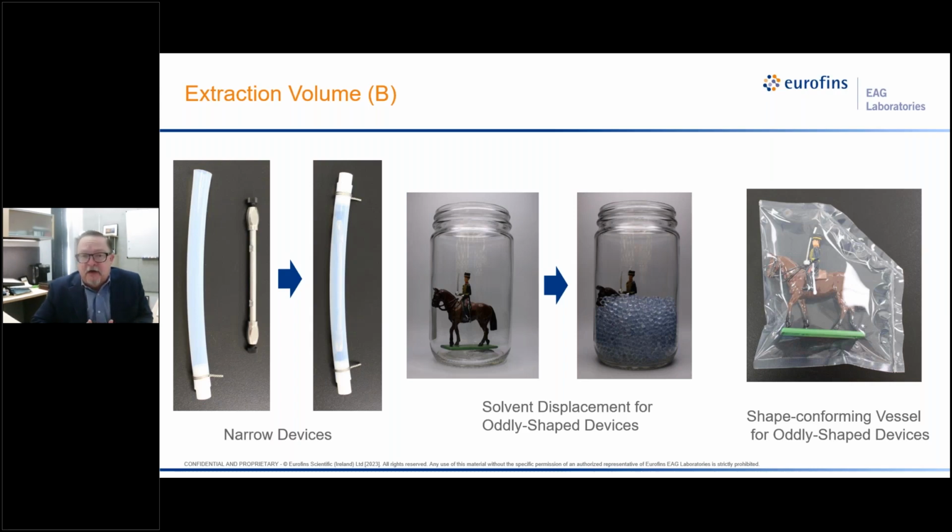Generally, you can pre-treat these devices, these added displacement tools that you're using, and try to minimize their contribution to the extractable profile. Another good strategy is Teflon bags. These Teflon bags are available in different thicknesses, and in some cases you can heat seal them. I wouldn't suggest doing that with flammable solvents, but in those cases where you can't heat seal, you're going to need to find good methods for sealing that device, or that enclosure.